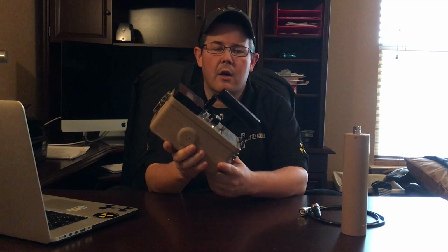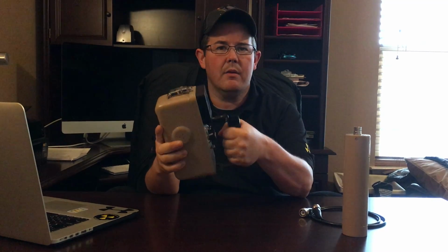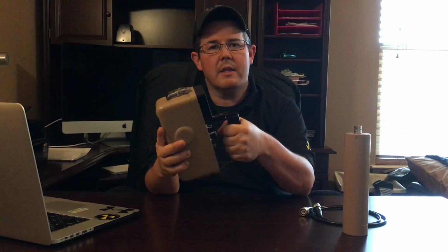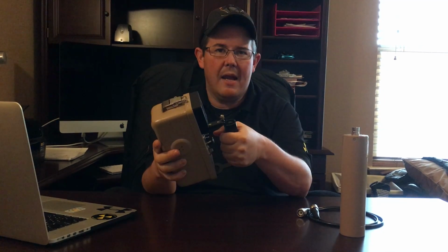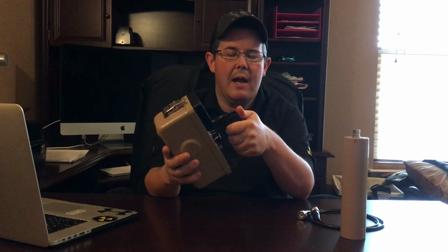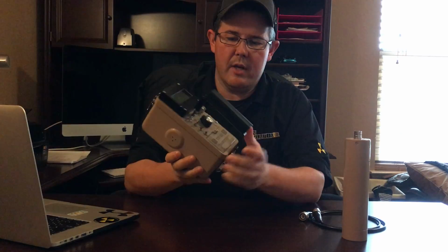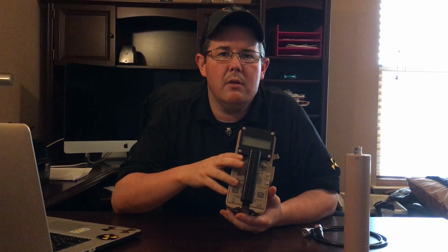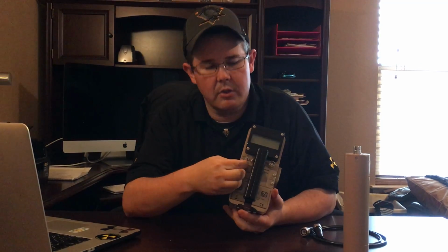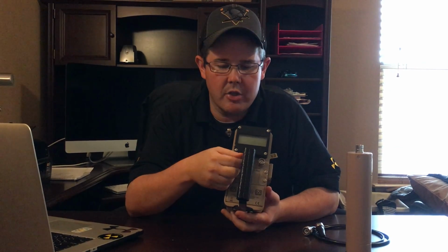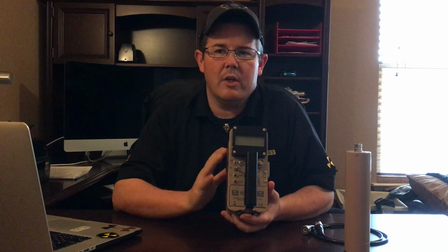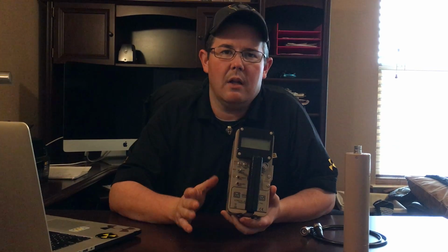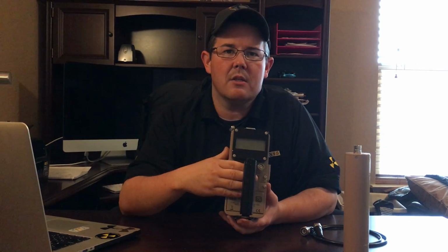One of the key musculoskeletal disorder occurrences that could happen is, of course, your hand grip being in an awkward position. It is not natural for your hand to grip this for many hours. That can cause issues and could even lead to things like carpal tunnel if you were doing it every day for multiple hours. All the buttons on the meter are little, so it's a little tougher to get in and change your settings. The great thing about surveying is that once you have your settings, it's usually good to leave them alone, so you're not always having to get into the dials.